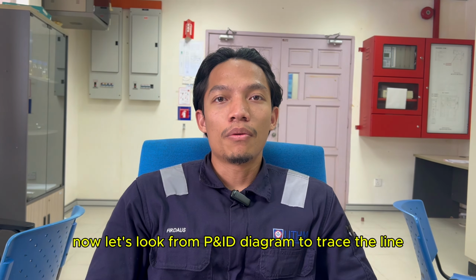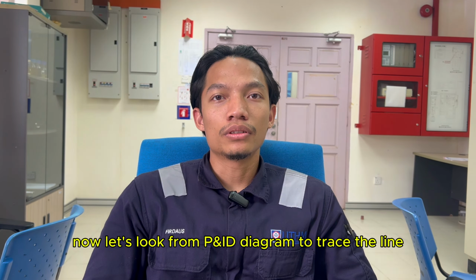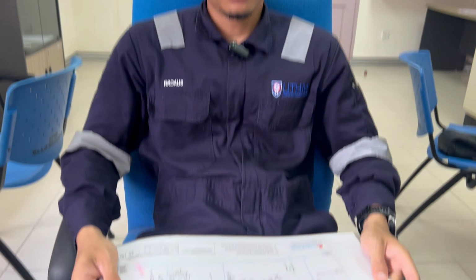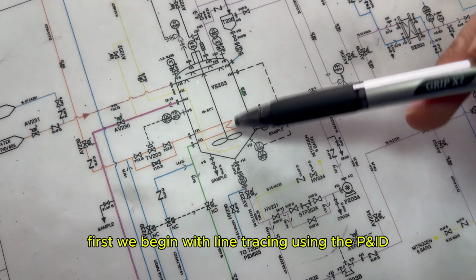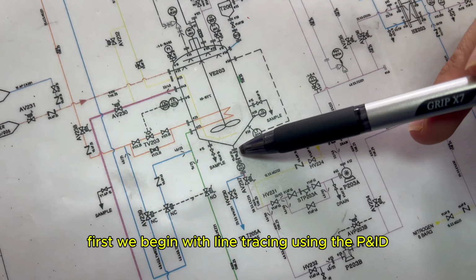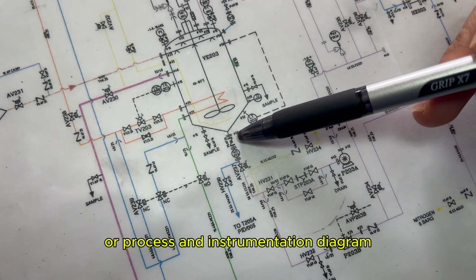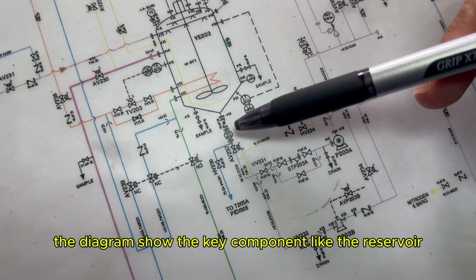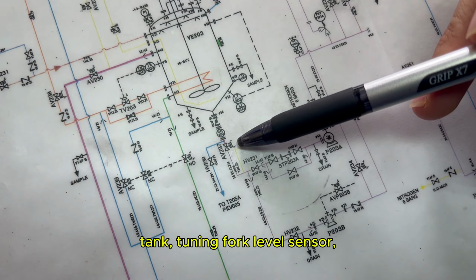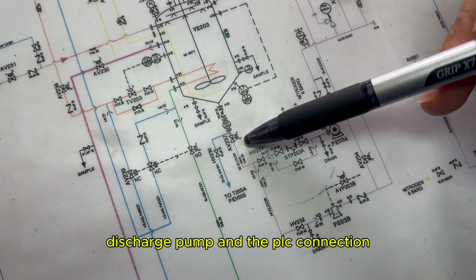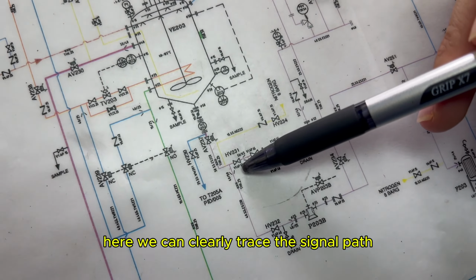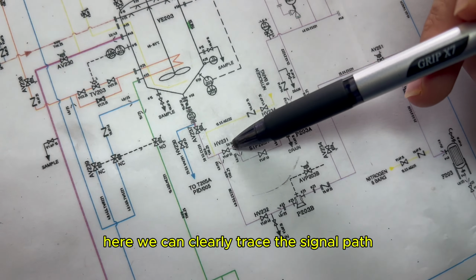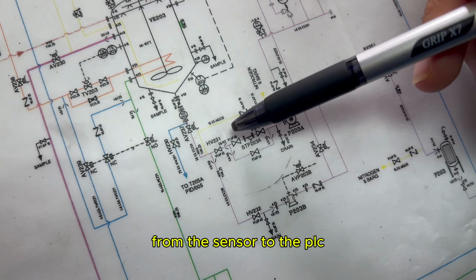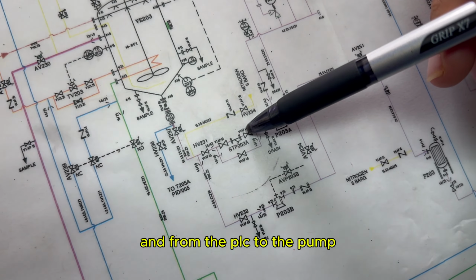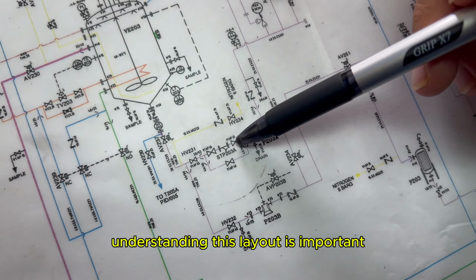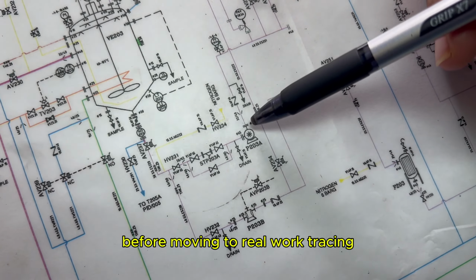Now, let's look at the P&ID diagram to trace the line. First, we begin with line tracing using the P&ID, or process and instrumentation diagram. The diagram shows the key components like the reservoir tank, tuning fork level sensor, discharge pump, and the PLC connection. Here, we can clearly trace the signal path from the sensor to the PLC and from the PLC to the pump. Understanding this layout is important before moving to real work tracing.